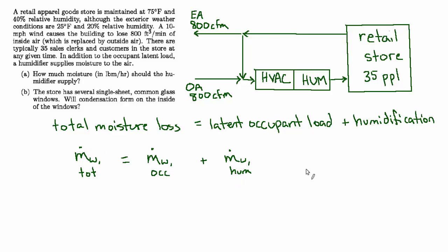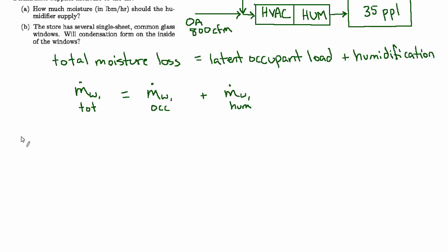So let's start with the occupants. We can take a look at Table 40.4—that tells us how much heat people produce at different levels of effort. So we'll say that these folks are standing or walking or doing light work. And based on that, I come up with a latent load, which is adjusted for the assumption that it's half male and half female, of about 200 BTU per hour per person.